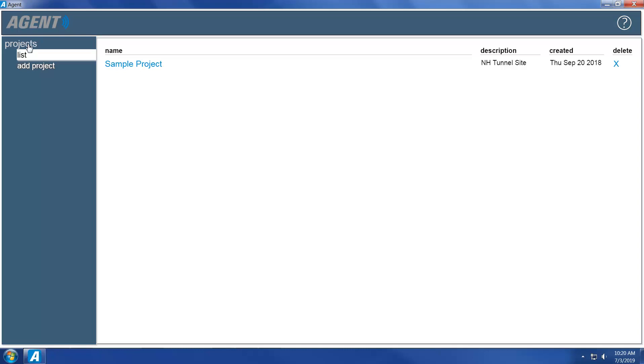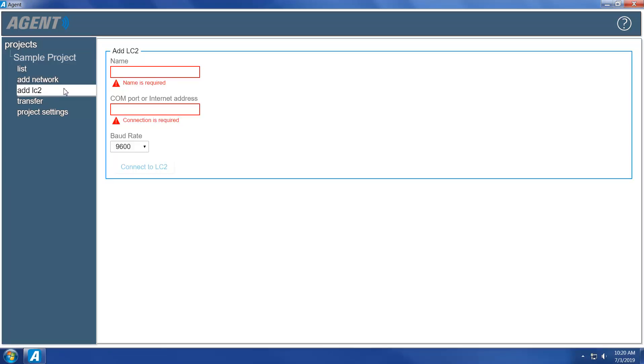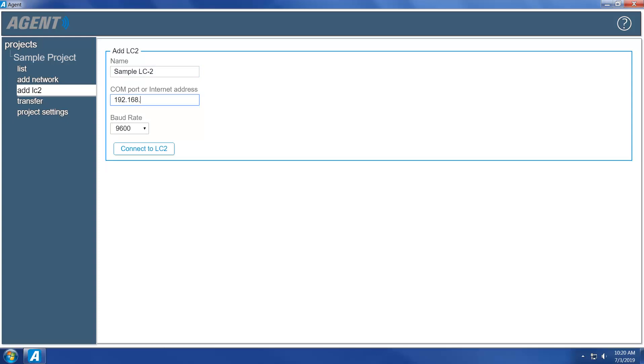To add an LC2 to a project, select the desired project, then click Add LC2 on the left side of the screen. Start by giving the data logger a name. If communication will be established using an external network device, enter the device URL or IP address into the COM port or Internet Address field. IP addresses must be followed by a colon and then the port number. If communication will be accomplished through a cable, type COM into the COM port or Internet Address field to open a list of active communication ports, then select the COM port the LC2 is using.